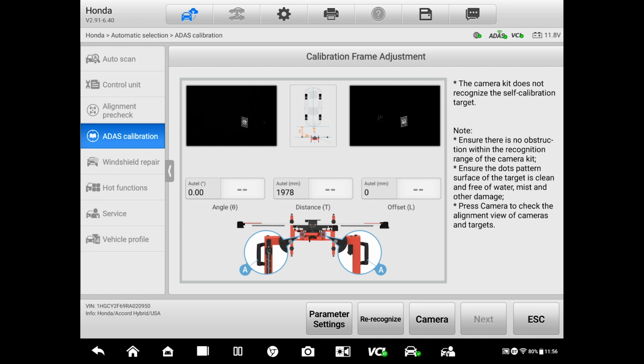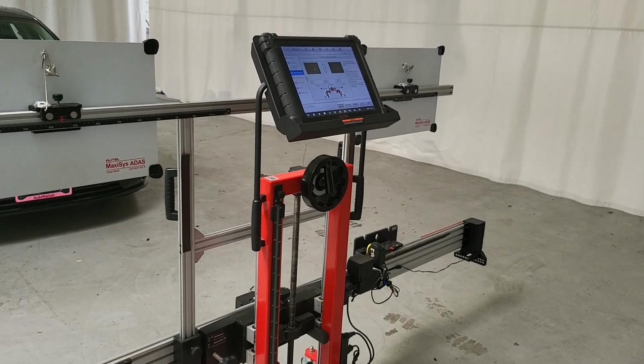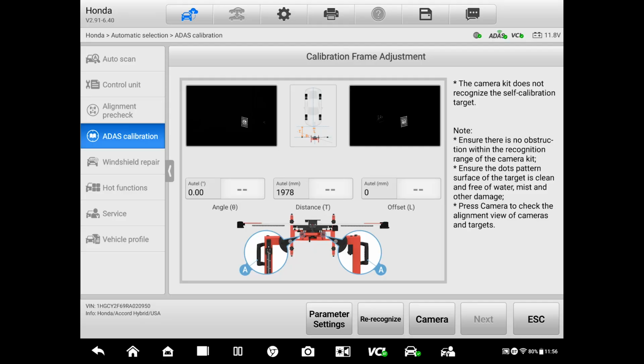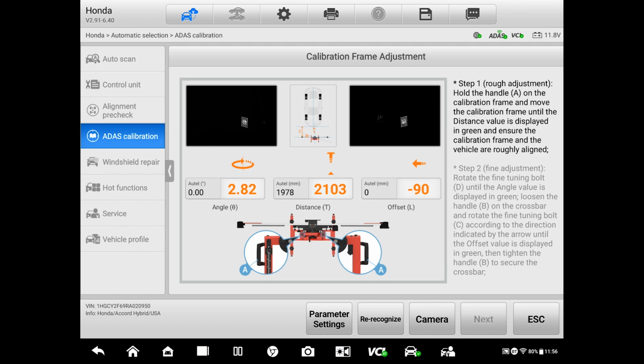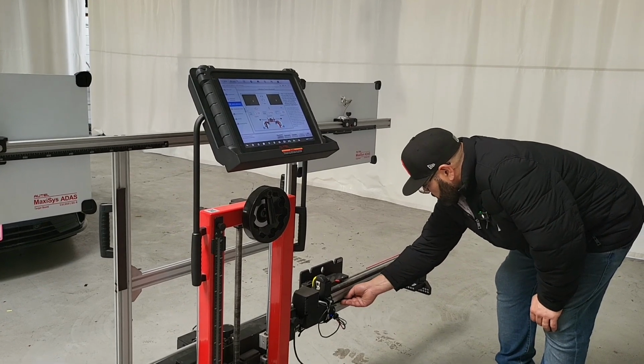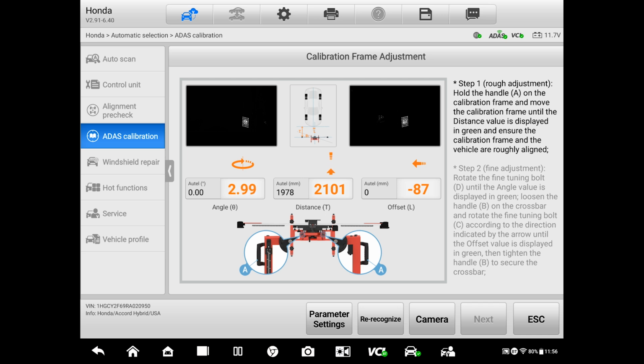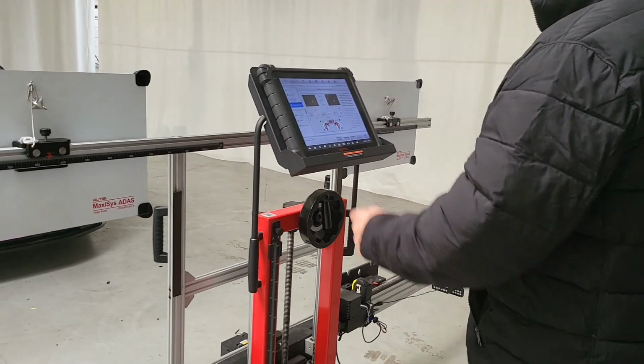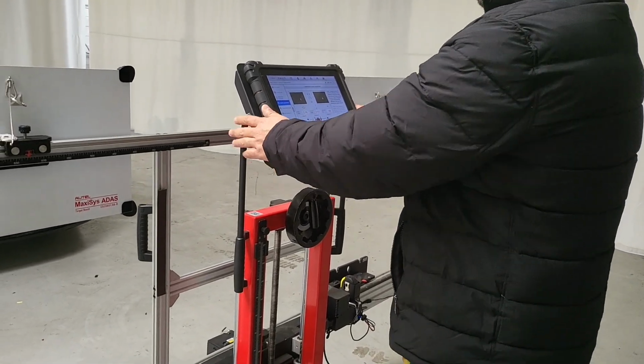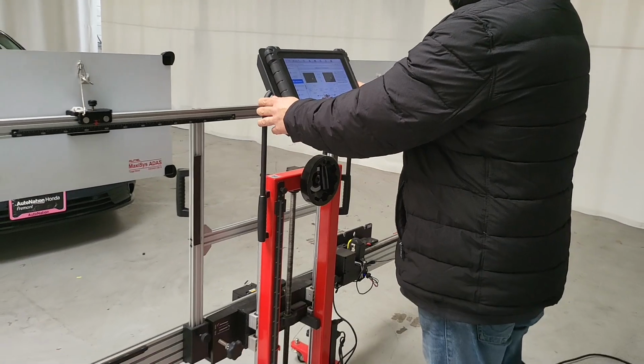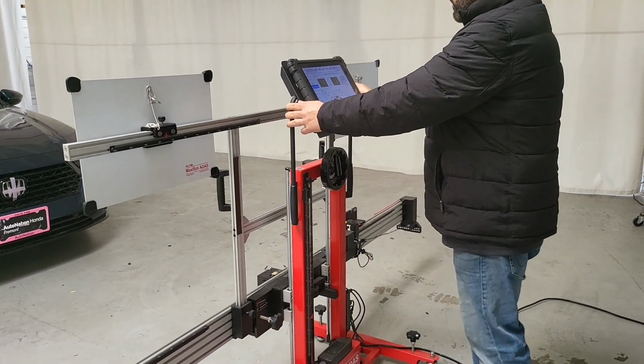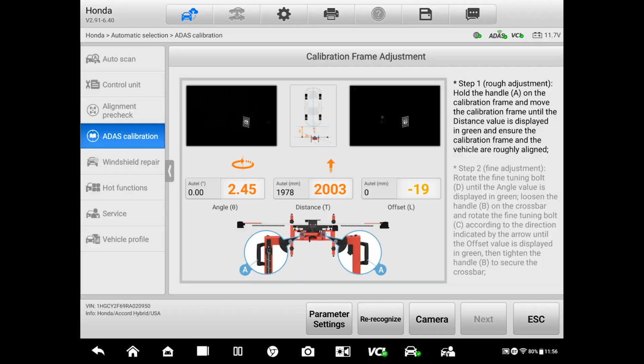All right. There's no wiring, there are no wires hanging there. Pull on that thing, this cable right here. Yeah, that's what it is. Leave it right here. It was blocking the self calibration. So there was a wire blocking one of the self calibration targets on the frame. So we're just going to bring that frame into the position that the scanner is calling for.